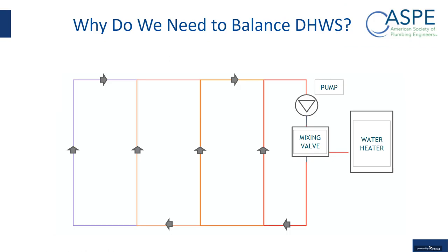Now that we're recirculating the hot water, the idea is that you turn on a fixture and the hot water is there instantaneously. The next point of the discussion is, why do you need to balance the domestic hot water system? Here we have a typical sketch of a domestic hot water system with 4 risers and no balancing.